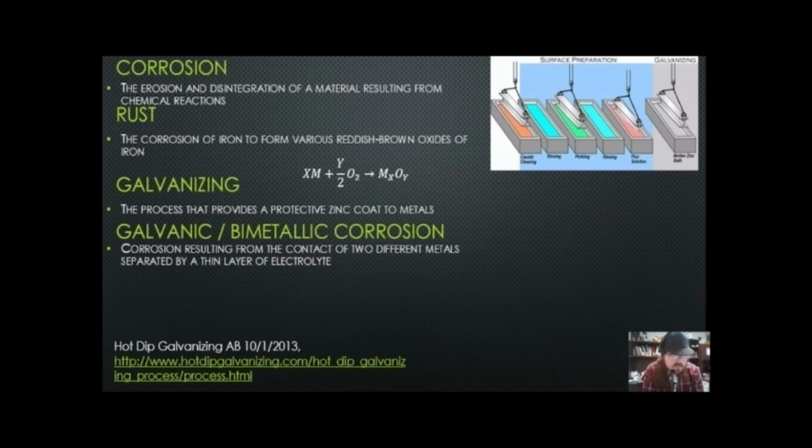All the zinc has fully corroded. In fact, on large underground tanks that are too hard to galvanize, they often add either magnesium, aluminum, or zinc blocks to them as a sacrificial electrode to help reduce the corrosion and make them last for a longer time.